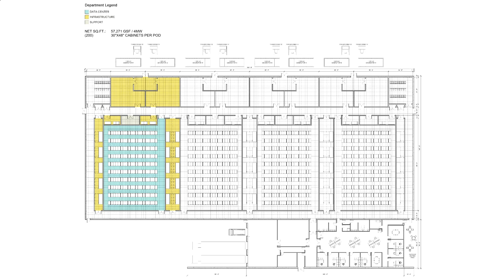Each of the pods would have generator capacity to your specifications. What's modeled here is a full 2N on the UPS, on the gen, on the room itself, the PDUs, and the transformers. We've envisioned this facility with DX cooling, but depending on where it is in the U.S., that might be modified to chilled water, whichever is more efficient for the space.